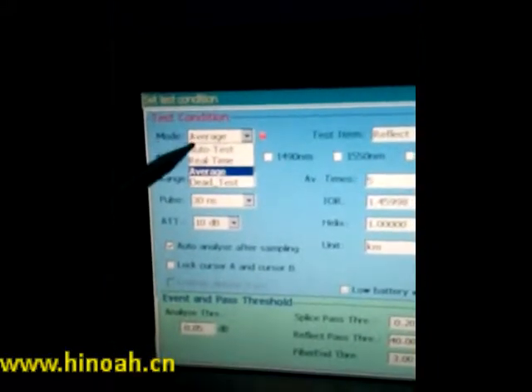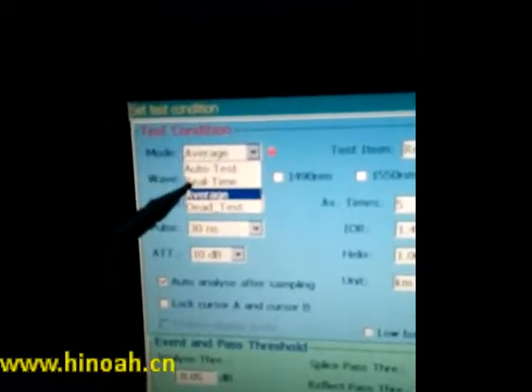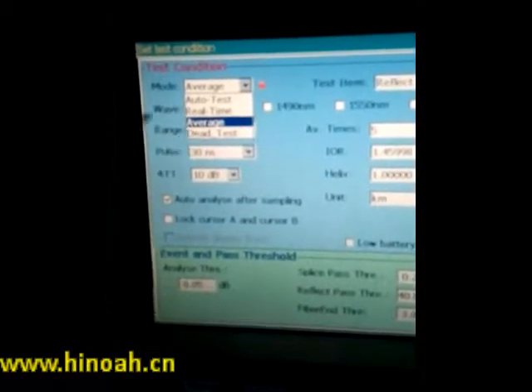The device also has an OTDR function. If we want to use it, press it, and we will show you how to use the OTDR function. Press Setup, and here you will see the configuration interface where you can set up the parameters used to test the lines. It has a Mode function with four testing options: Auto Test, Real-Time Test, Average, and Dead Zone Test.